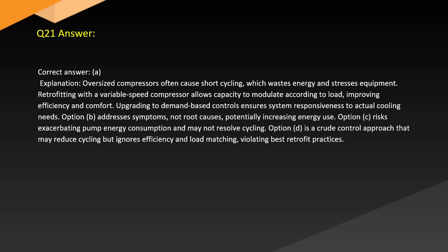Answer. Correct answer. A. Explanation. Oversized compressors often cause short cycling, which wastes energy and stresses equipment. Retrofitting with a variable speed compressor allows capacity to modulate according to load, improving efficiency and comfort. Upgrading to demand-based controls ensures system responsiveness to actual cooling needs.